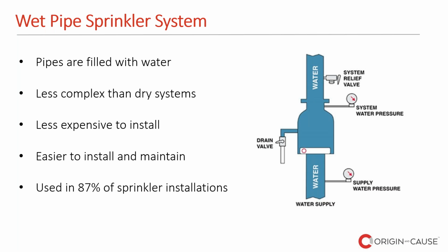Just going over what a wet pipe sprinkler system is, very quickly, if you see the graph here, the entire system is filled with water. It's a lot less complex than the dry systems, less expensive as well to install compared to a dry system, and it's very easy to install and maintain. It is used typically in about, you could say, 90% of all sprinkler installations. And again, one of the main advantages is that it's simple, reliable, effective.